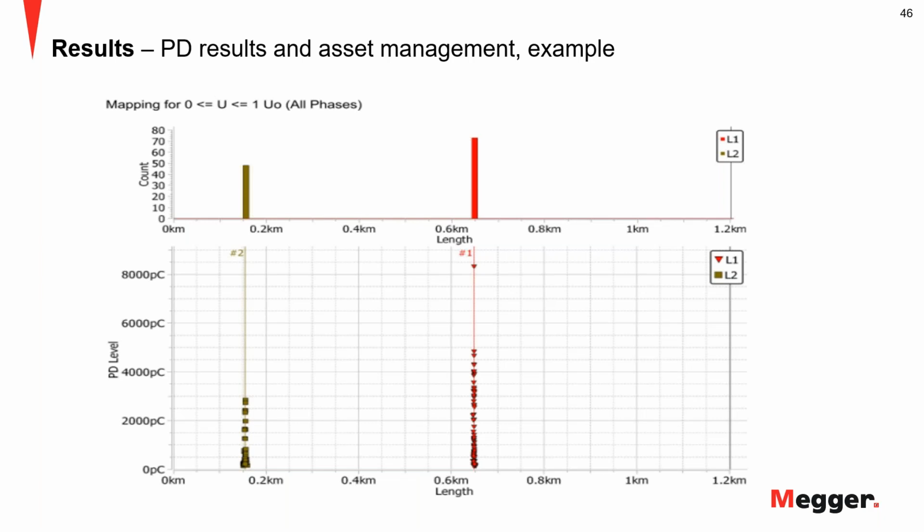And you can pretty much say, even if you don't know where the splices are, these two things with a very high probability are splices, even if you don't know where they were or that they were there, because it is most likely an accessory problem, which means splice. So this is the data you see.